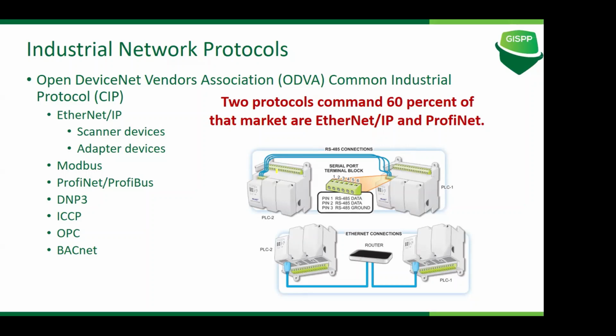So DNP3's mostly utilization is, okay, you are sitting inside the SCADA system, you are sitting on SCADA screens, and you need to talk to any PLC there only. It will not be used like Modbus. Modbus was used from SCADA to RTUs, remote telemetry units sitting somewhere in another part of the world and sending something over Modbus. But here, like I said, the data is coming from RTU to DCS, DCS to SCADA, and SCADA to PLC. So now SCADA and PLC are preferably talking in the DNP3 standard because it is being referred by NERC, the American national grid regulator of the power sector. And if they are a part of the power sector, SCADA will be talking to the PLCs of electric system grids in this protocol, DNP3.